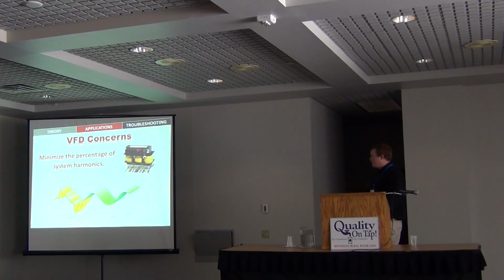You can use an input line reactor, that's what this is. This goes ahead of the VFD, and it opposes rapid changes in current. Other things we can do, we can install 18 pulse VFDs. Most VFDs, the off-the-shelf little box that's normally about this big, if it's 20 horse or so, is a 6 pulse drive. 6 pulse drives go up to 200 horsepower. Then you want to start looking at, instead of a 6 pulse drive, maybe we go to 18 pulse. And what an 18 pulse drive does is create that many more pulses of that modulated signal to get that much cleaner of an output to the motor.